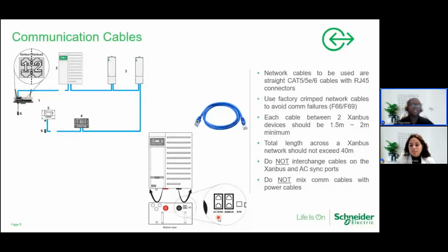Because if they don't start together at the same time from 0 to 230 back to 0, then negative 230, you're going to have a lot of very weird voltages across the network and it could end up damaging your load. So the AC sync is to help with extra stability of this multi-unit system. So do not mix Xanbus ports with the AC sync ports. Make sure you have your cables properly tagged to know Xanbus is going to Xanbus and AC sync is going to AC sync, because if you interchange them, a lot of issues would happen to the system, which is what we're trying to avoid. So make sure they're properly tagged and you won't have any issues there whatsoever.